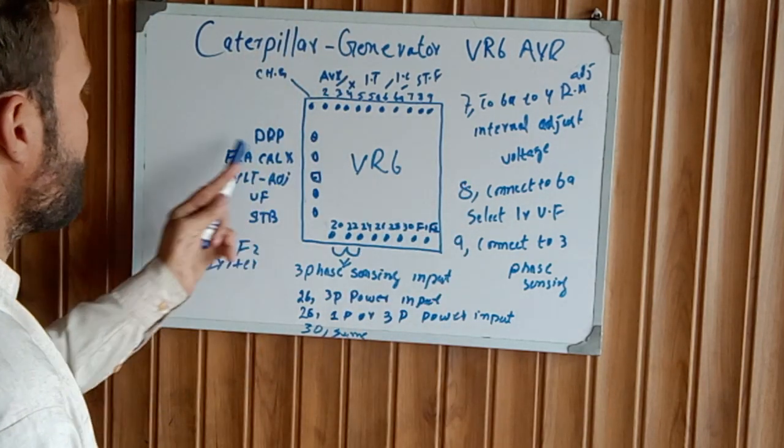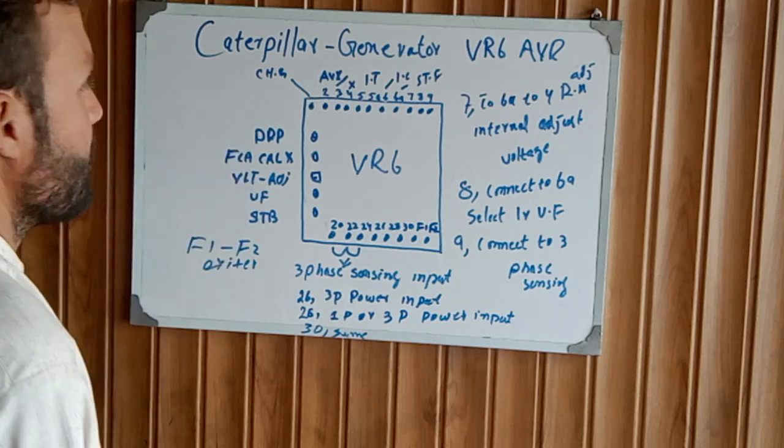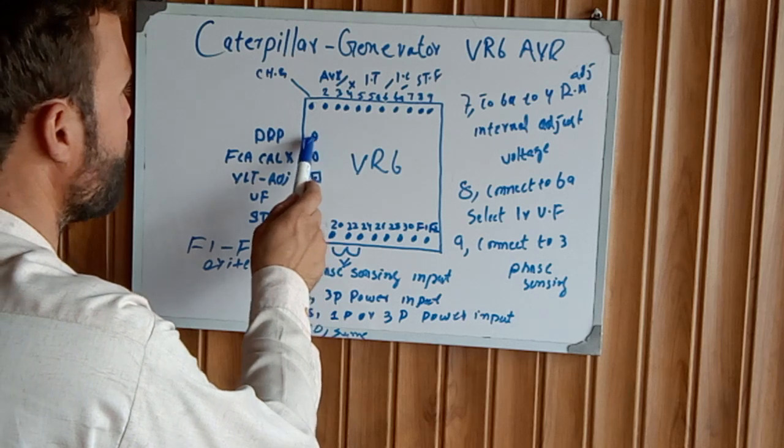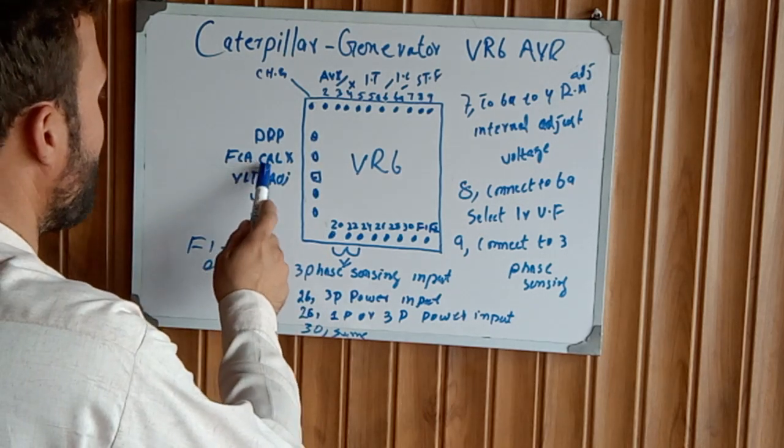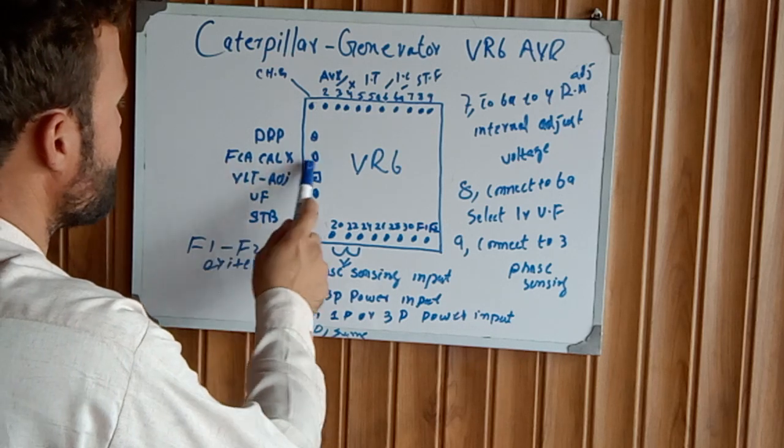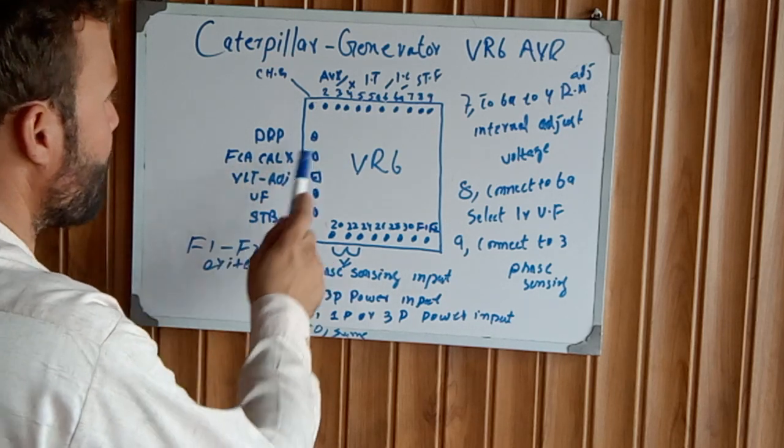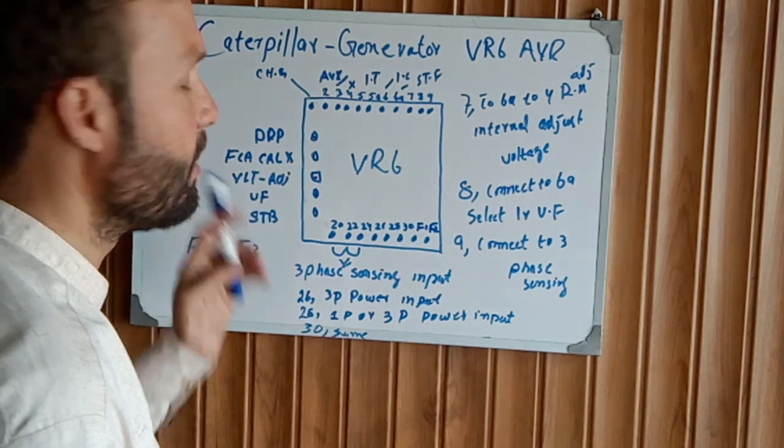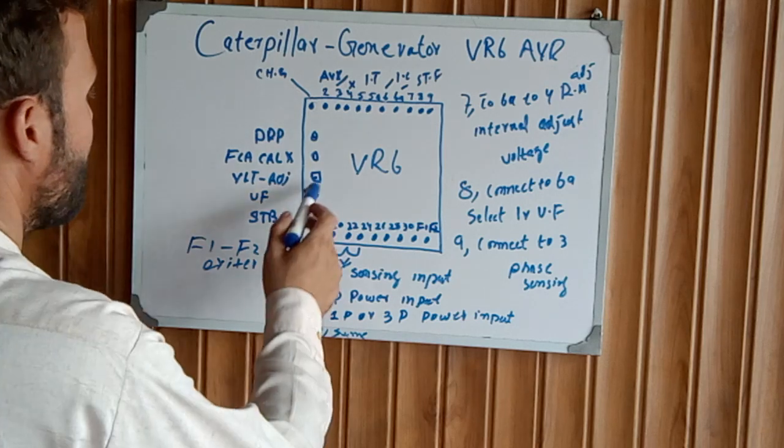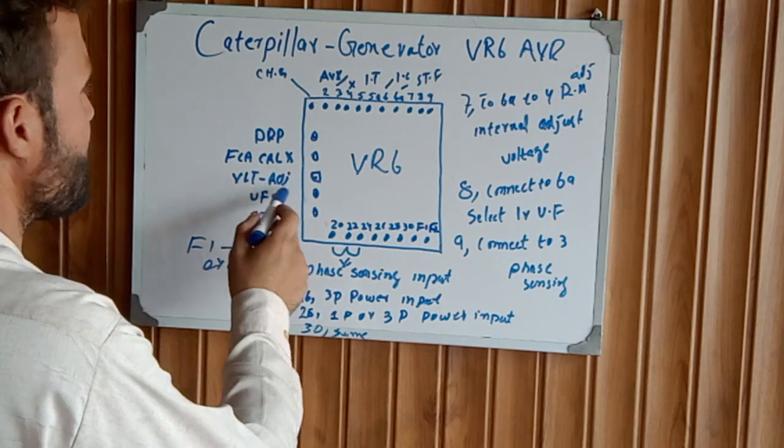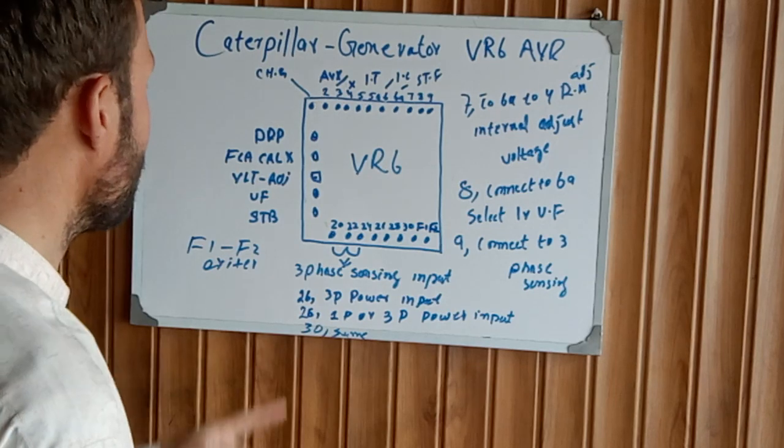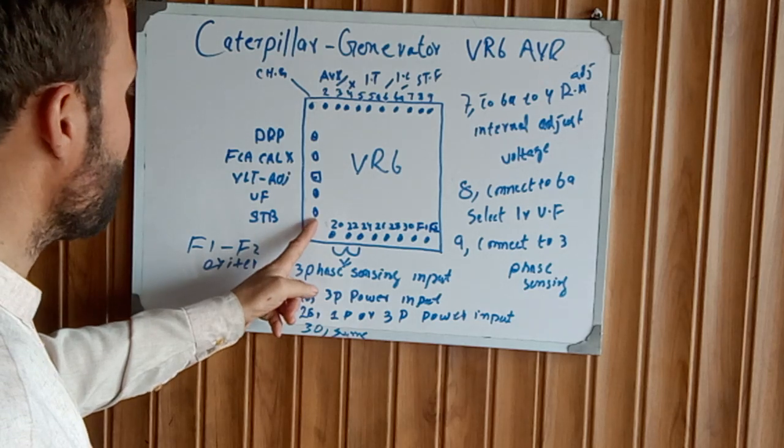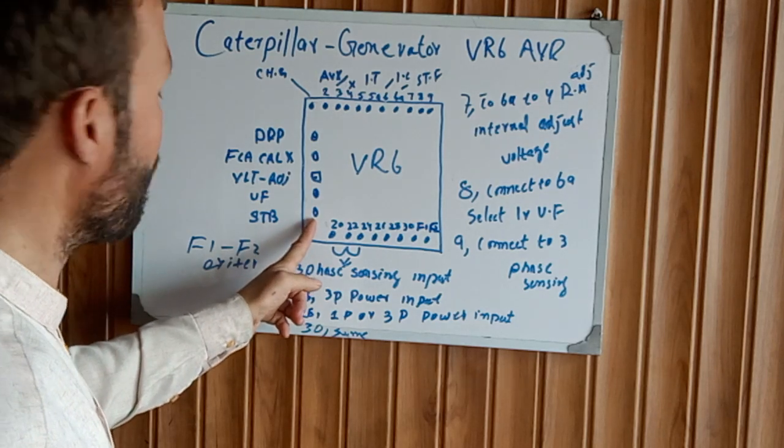This is the top terminals. The left side adjustable, this is for the droop setting. This small potentiometer, FCA CAL, this is the company adjustable. It doesn't need to be adjusted. This is the factory adjustable. This one, the third one, is voltage adjustable potentiometer. And this one is the under frequency adjustable potentiometer. And this one is for the stability of the voltage.